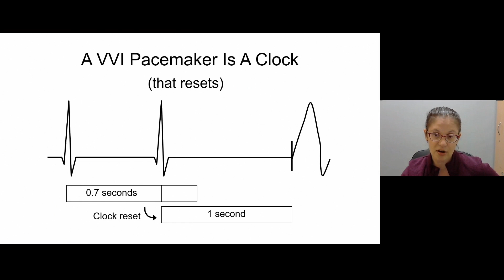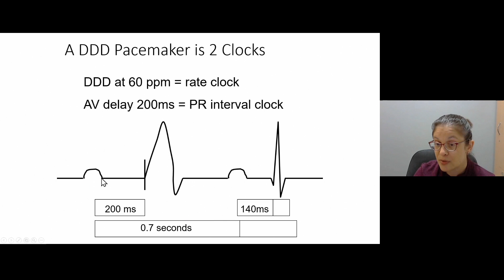So a dual chamber pacemaker has 2 clocks. It has the heart rate, and then it has the PR interval, which we call the AV delay, which in this case we've set to 200 milliseconds. Here I put these together as one tracing just for simplicity, but inside the pacemaker they're separate. There's a tracing for the atrial lead and there's a tracing from the ventricular lead that are kept separate. Here you have a P wave that the patient has. The device waits 200 milliseconds to see if there's going to be a QRS complex. And if there's not, it paces the ventricle and produces a QRS complex. At the same time, the atrial lead is waiting for the next P wave to occur. And if that had gone more than a second, it would pace the atrium as well.